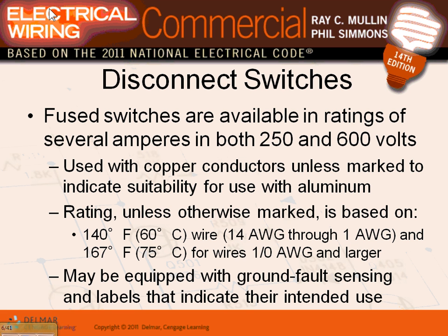Fuses. Your fuses, guys, most of the time, I'm looking at a fuse here. I'll pass these around if anybody would like to look at them. The fuses are rated for 600 volt. Most of us are 600 volt, or your fuse is 250 or 600 volt. A lot of equipment, guys, for example, this 250 can handle the following: we had 240 system, 208 system. The 600 can handle 480 system and 600 volt system, right?